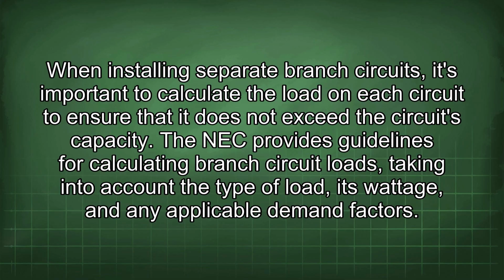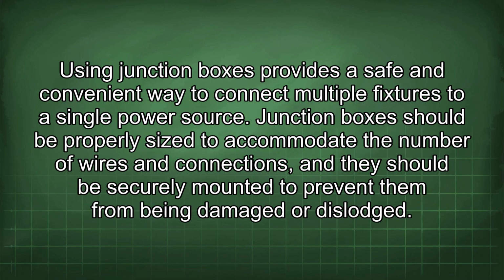When installing separate branch circuits, it's important to calculate the load on each circuit to ensure that it does not exceed the circuit's capacity. The NEC provides guidelines for calculating branch circuit loads, taking into account the type of load, its wattage, and any applicable demand factors. Using junction boxes provides a safe and convenient way to connect multiple fixtures to a single power source. Junction boxes should be properly sized to accommodate the number of wires and connections, and they should be securely mounted to prevent them from being damaged or dislodged.